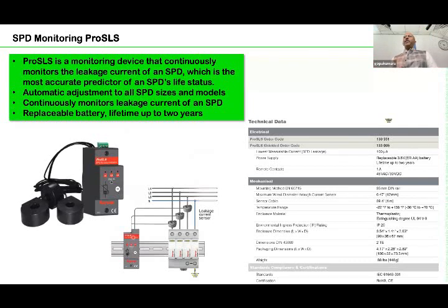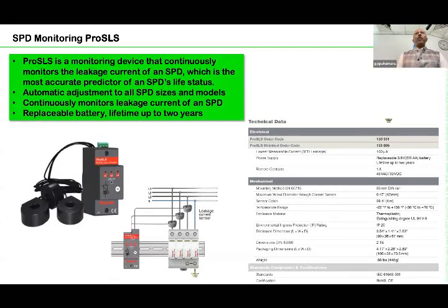Also, the one which I am showing is for leakage current measurement, because if you go for a 4+0 connection, there can be leakage current once the SPD deteriorates, and that leakage current may create other problems such as shock. So these devices can be used to measure the leakage currents. These are especially required for a high-tech, highly critical installation.